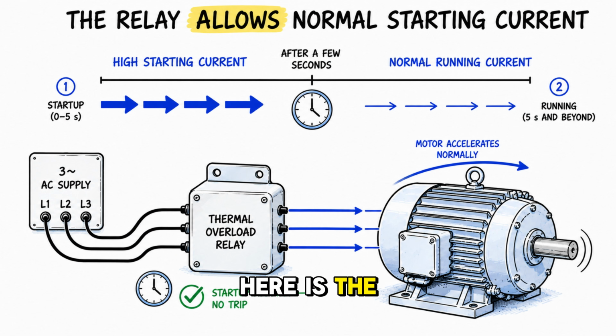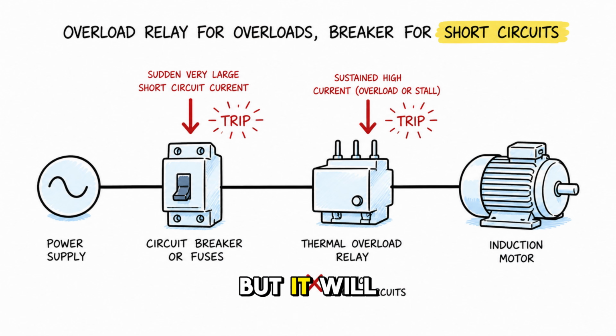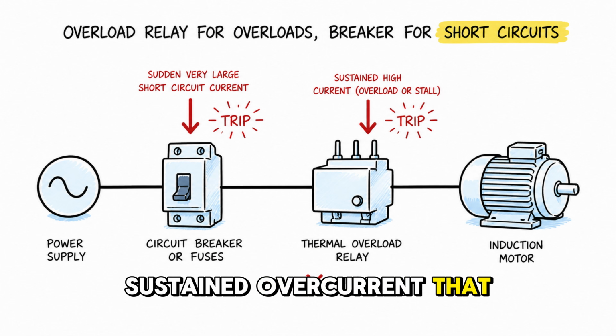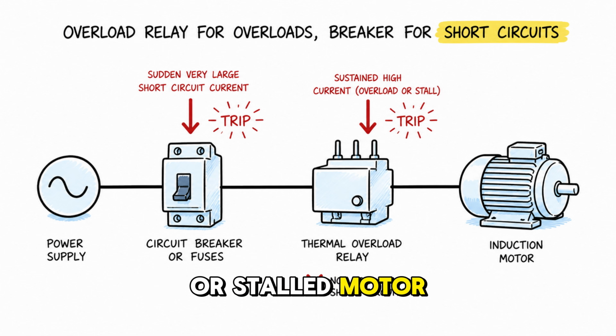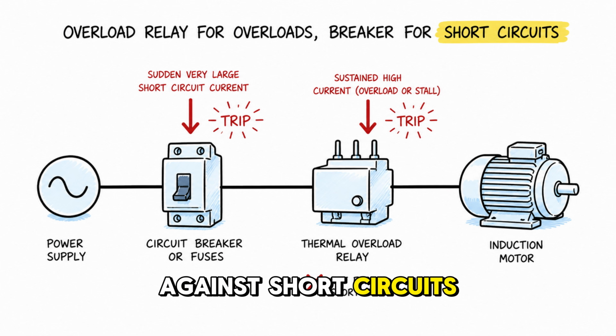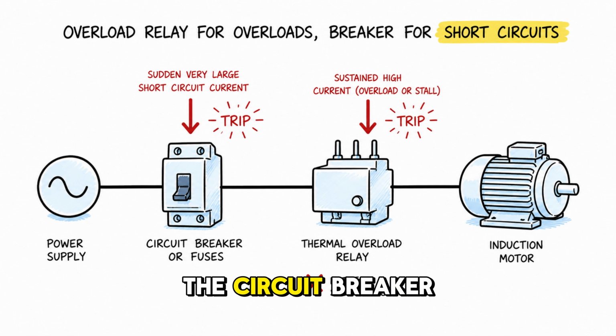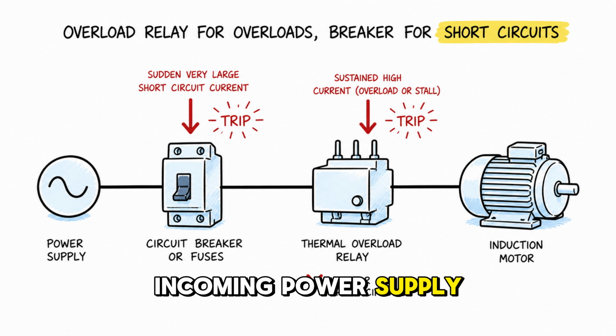The key feature here is the time delay. A thermal overload relay allows the high starting current to flow for several seconds without tripping, because it recognizes this as a completely normal startup event. But it will trip on a sustained overcurrent that indicates an overloaded or stalled motor. The thermal overload relay does not protect against short circuits. That is strictly the job of the circuit breaker or fuses on the incoming power supply.